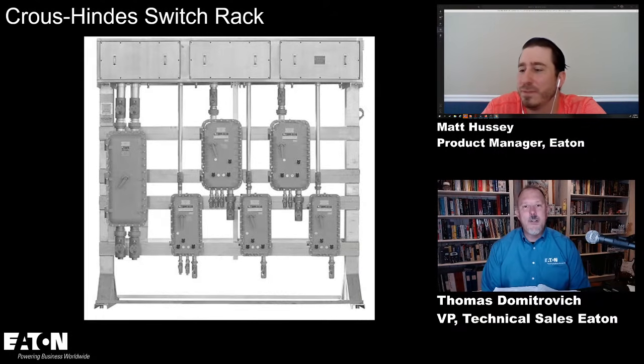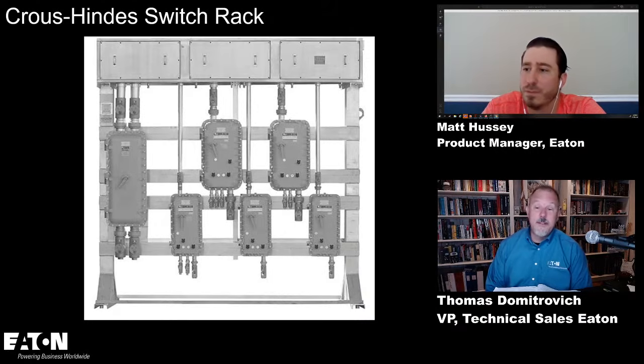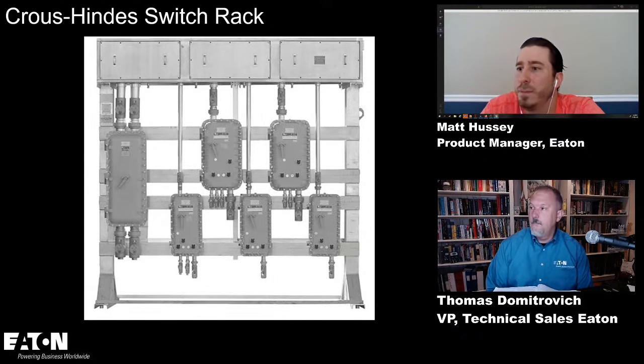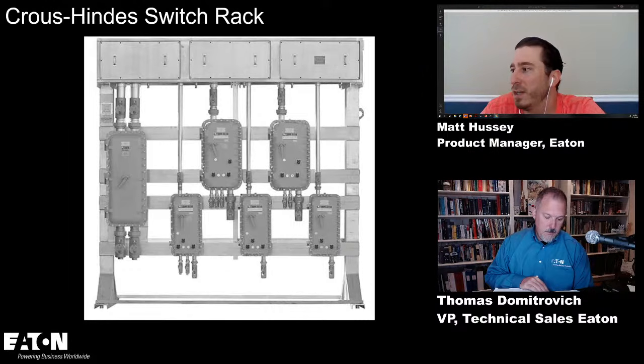And you know what's funny is I saw one of these down at the Houston Experience Center, and I didn't know they had a specific name for it. I just thought they put a bunch of parts together and made some controls there. But it's a listed switch rack for a hazardous location, and that's like your MCC, but just for a HAZLOC location. Yep. And the bus or power conductors are routed at the top there, and then each unit is fed off of that. Excellent. And they also have to consider some things like purging for certain environments and things like that.